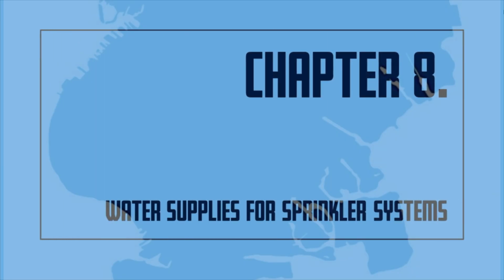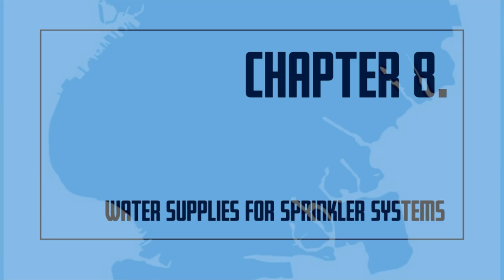Chapter 8. Water supplies for sprinkler systems. The sources used to supply water to sprinkler systems are the same as those for standpipe systems. Sprinklers may be supplied from one or a combination of sources. For example, they may be supplied by public mains, gravity tanks, pressure tanks, fire pumps, reservoirs, rivers, or lakes.